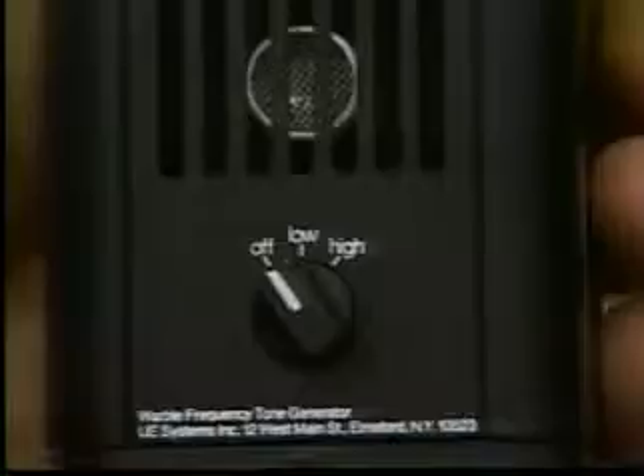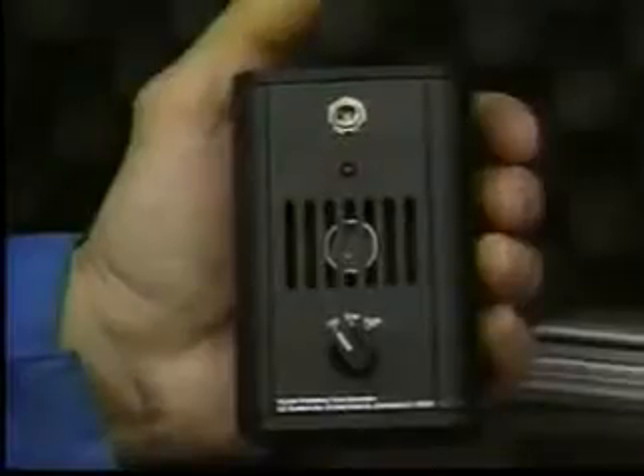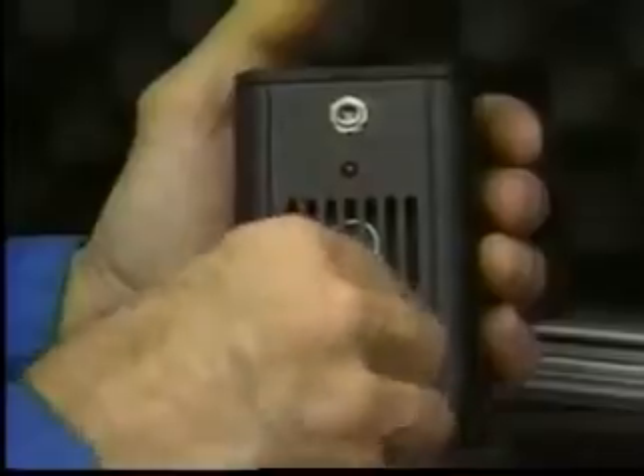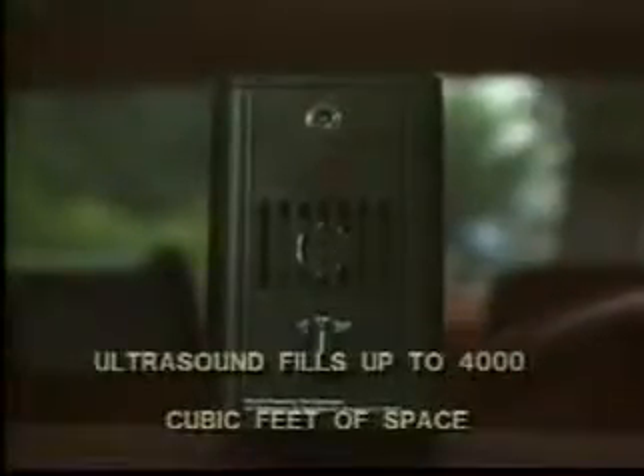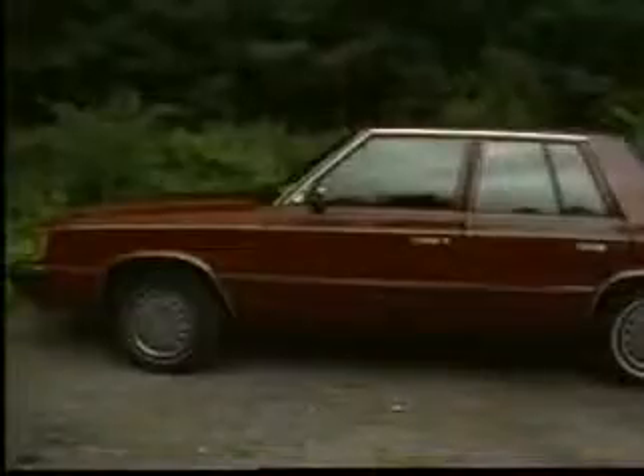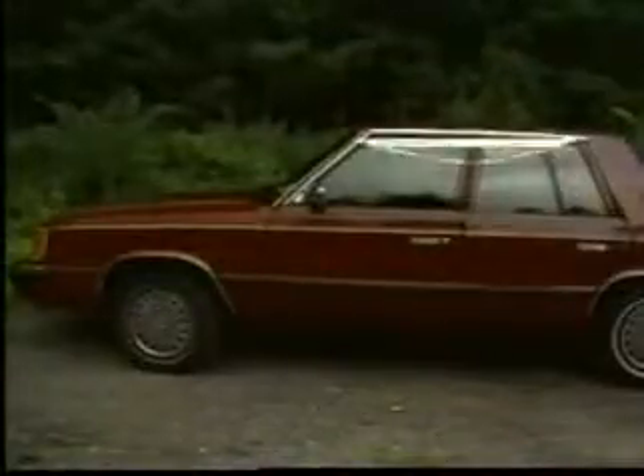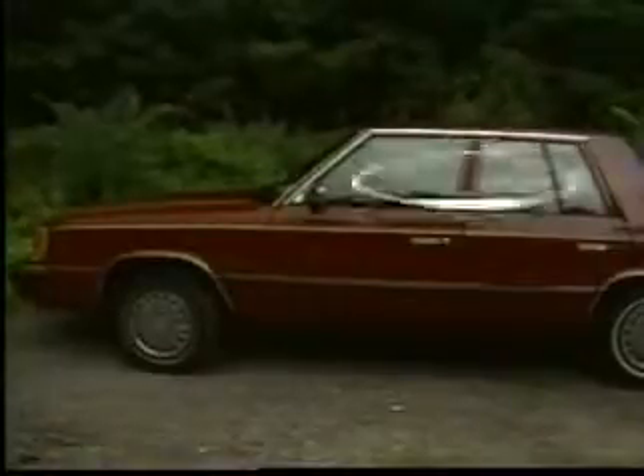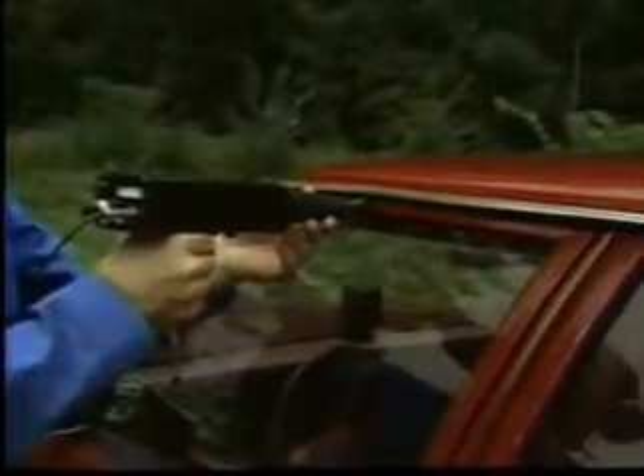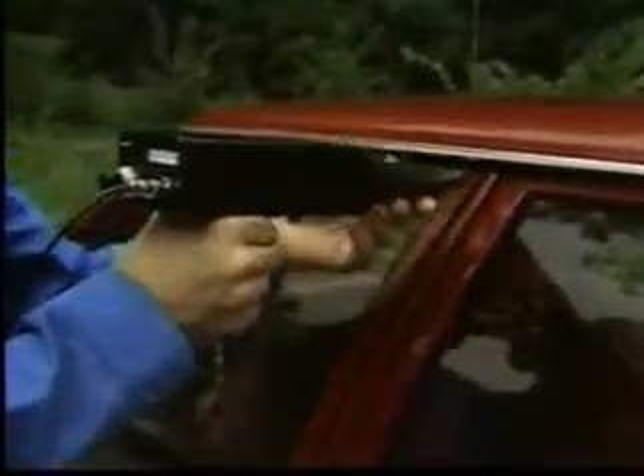Now let's discuss use of the warble tone generator. The tone generation method can be effective in situations when it may be difficult to pressurize or create a vacuum. The tone generator is placed inside the item being tested. Ultrasound is then transmitted, filling up to 4,000 cubic feet of space. Because ultrasound is a short-wave signal, it deflects off solid surfaces, but will penetrate any pinhole leak. The same scanning method described earlier, used on the other side of the test surface, will pick up any escaping ultrasound indicating a leak site. Listen to the ultrasound penetrating this seal.